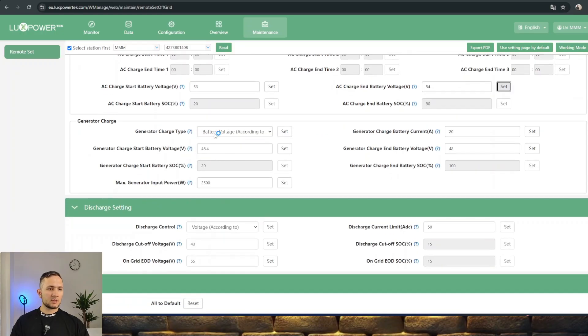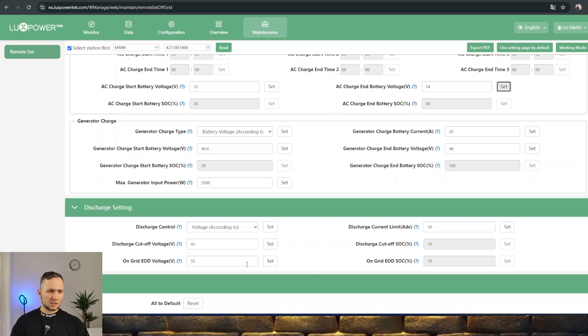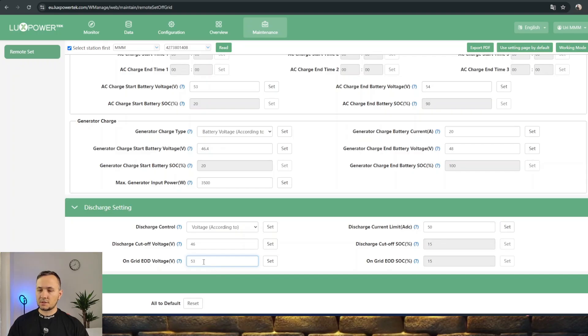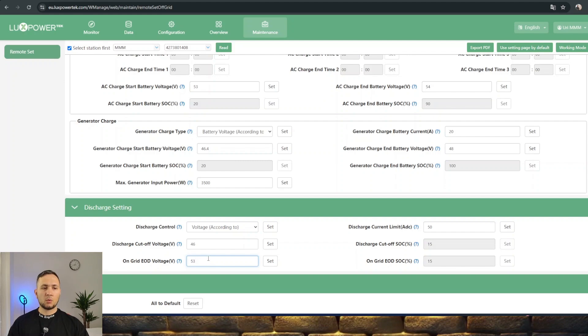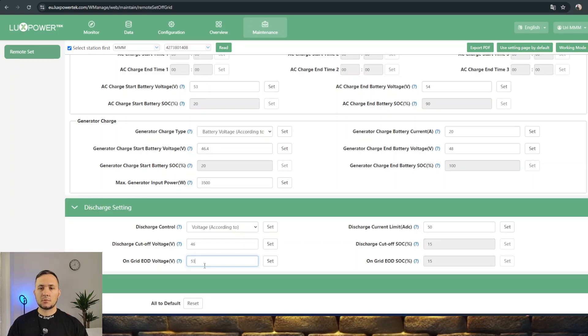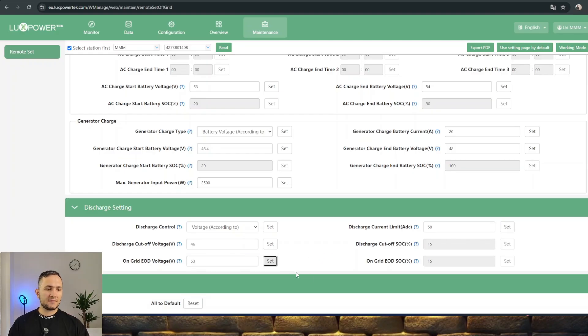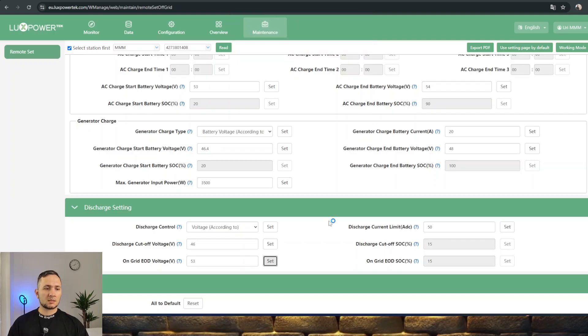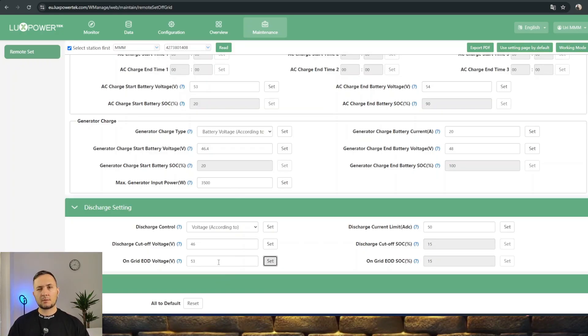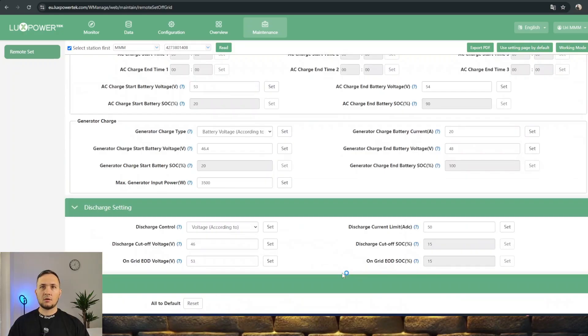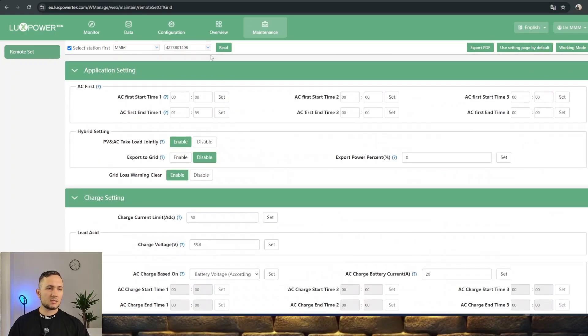Here's generator charge settings and discharge settings. The on grid EOD voltage is the minimum voltage that will allow the battery to discharge to when grid is available. When your battery is discharged to this number, it will switch to provide consumption by solar power plus grid power without using battery power. Let's put here 53 volts since the battery is now at 55. That's about 15% of total capacity. This is all you can see in end user access.